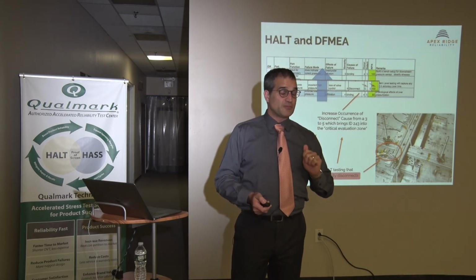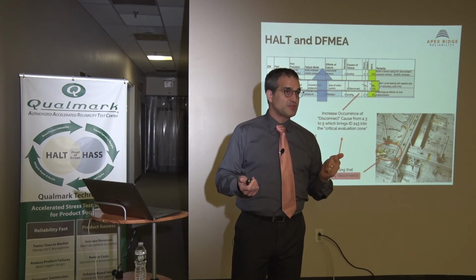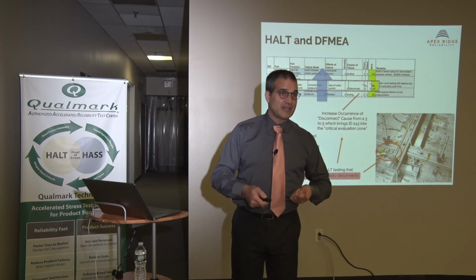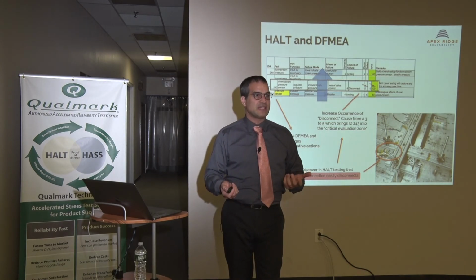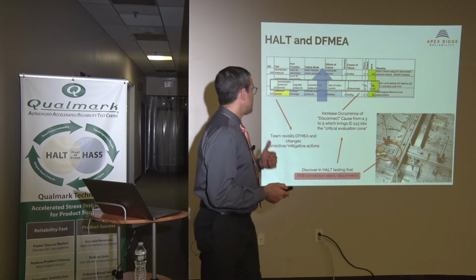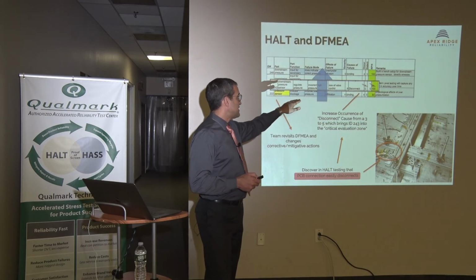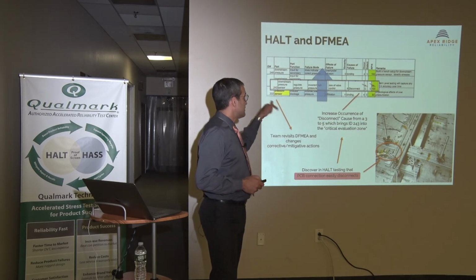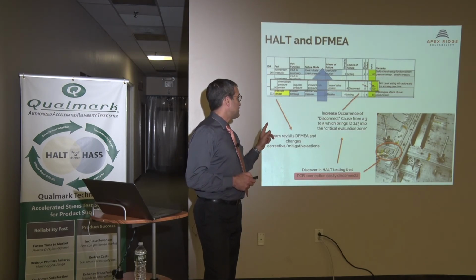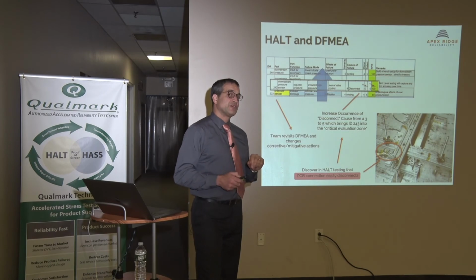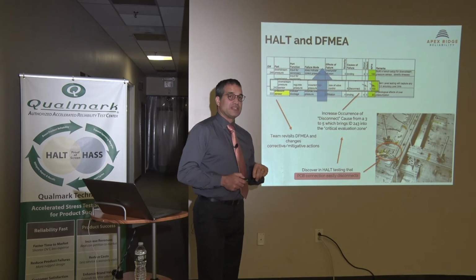We were really surprised. We're like, holy crap, that thing just pops right off. And remember I said it's hard to characterize how a doctor uses something in the patient and what's happening? We really realized how high a risk that was. So through that, we actually changed rankings on a different line item that was much lower. It had a ranking of 50. And now with the new ranking, for likelihood of occurrence of that being higher, it actually ended up rising right to the top.